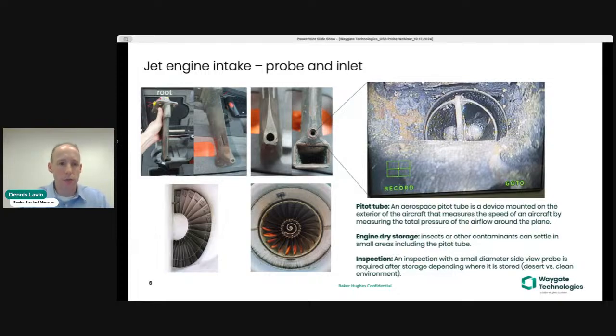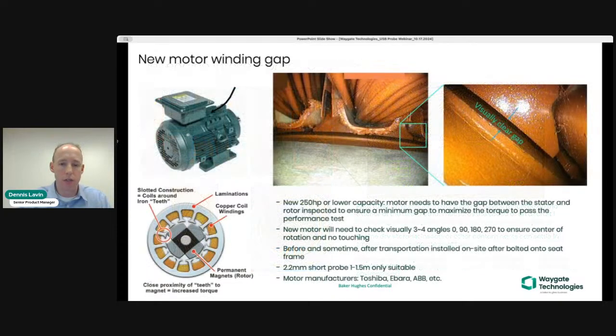So moving on to the next one, I think we have one on general industrial. This one's on a new motor, just in an industrial setting, manufacturing. A lot of times there's these motors. This particular one is on a 250 horsepower motor. And the inspection that needs to happen is to look at a gap between the stator and the rotor to ensure minimum gap to maximize torque, so it can pass the performance test for efficiency.